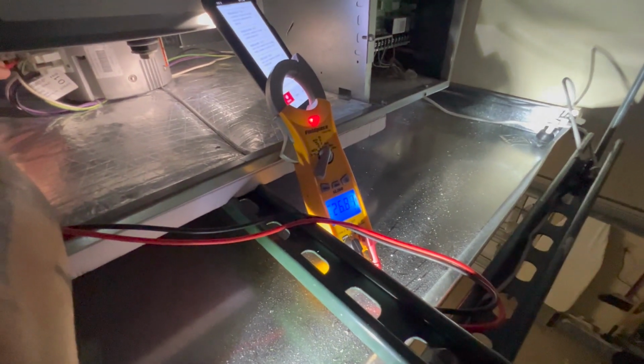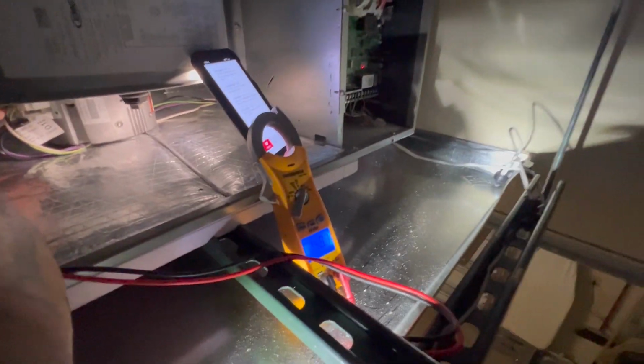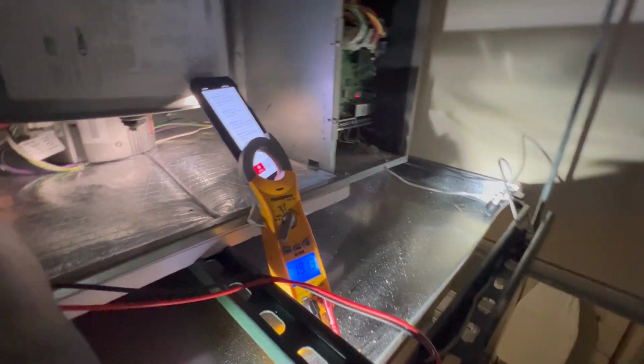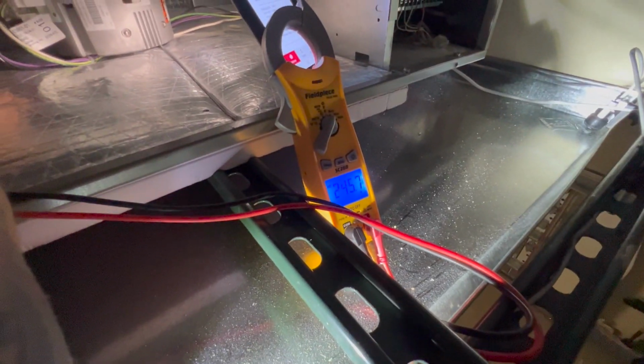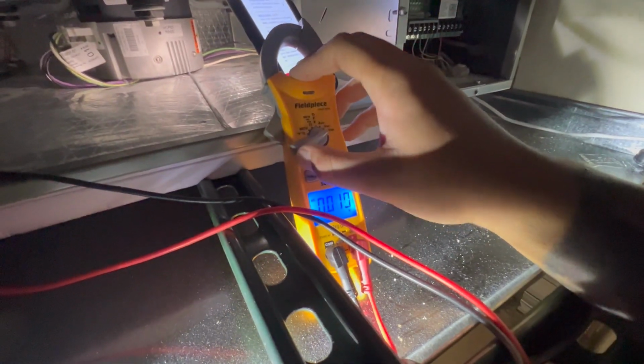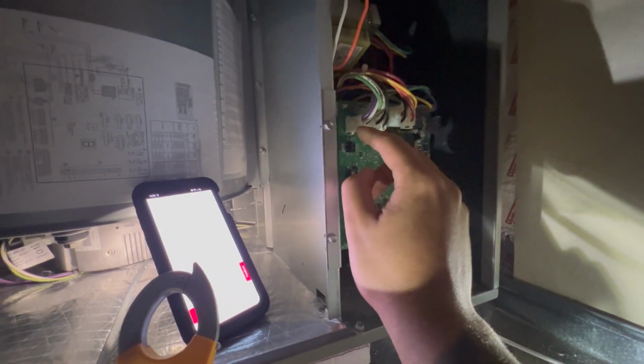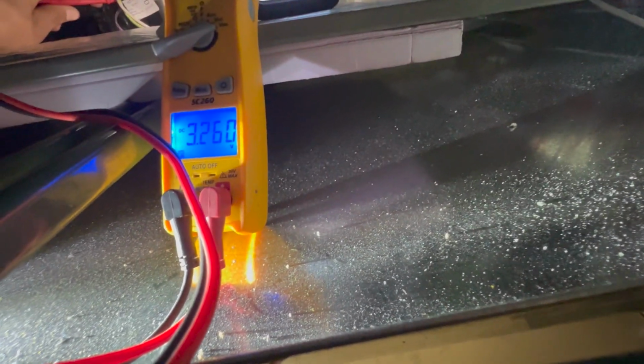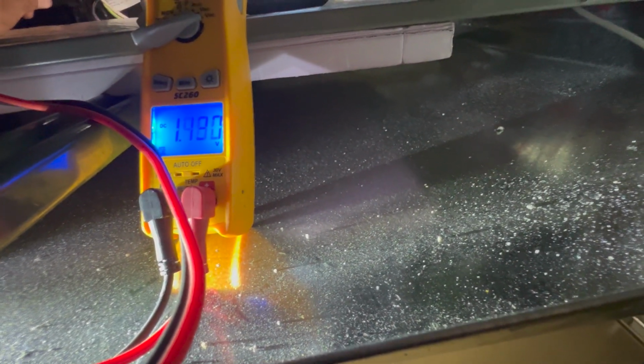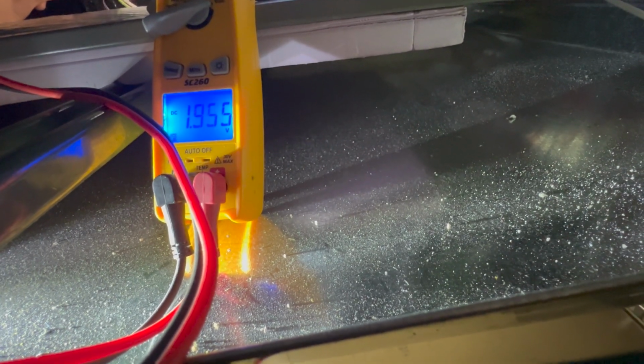So now before ordering any blower motor, we're gonna make sure we got high voltage and low voltage going to the blower motor. So we got, 1 second, so we got 245. Okay, so we do have high voltage. Now we're gonna change to DC because it's coming out of this plug as a DC power. In this case, your middle wires are gonna be your poles.